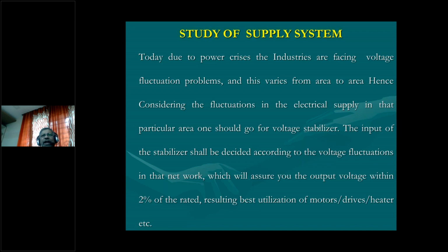The voltages get corrected. What happens? Suppose there is unbalance in the R, Y and B phases. Suppose instead of 240 volts, you are getting 245, 248 and 241. This difference is going to remain the same at the output side. You will not get a balanced voltage because you are sensing, and the three dimmers are controlled by a single servo motor. So there is another type of servo stabilizer, which is considered the unbalanced type. There are three different dimmerstats with three servo motors. The individual phase correction is sensed there and correction is done. So irrespective of any unbalance in the input voltage, your output voltage will be 415, 415, 415, or rather 240, 240, 240, plus or minus hardly 1 or 2%.